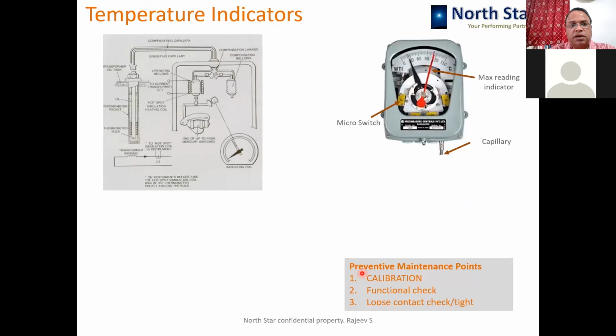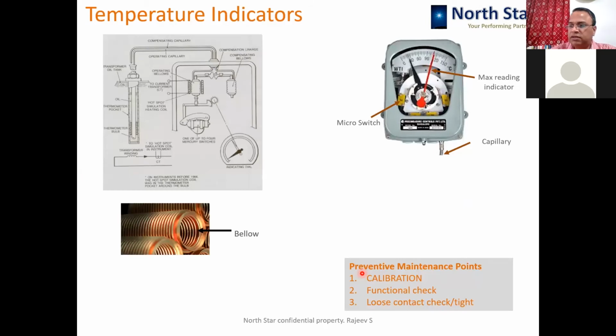Now temperature indicators are basically giving you the thermal image of the transformer loading and temperature. Here is a bellow, which is nothing but a mechanical device, like a spring, and it expands when the oil inside it is getting heated. As the oil is expanding, this bellow expands, and this increase in the length of the bellow is converted into movement of the pointer. So this is how you get the indication of the temperature.